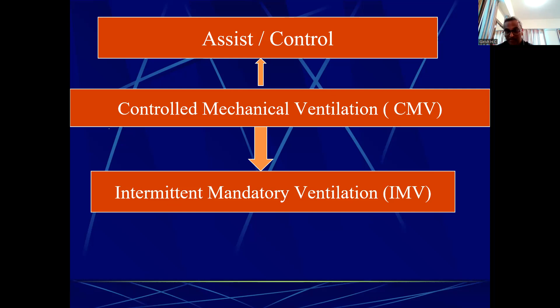Then intermittent mandatory ventilation. So the problem with assist control was that every time the patient made an effort, it gave a breath. That means if the patient is breathing 60 per minute, it gives 60 breaths, with a lot of pressure. So there was a chance for hyperventilation, because the technology was not there to allow the patient circuitry so that the patient can breathe normally in between the mandatory breaths. So that came later as intermittent mandatory ventilation. But still, this was not good enough, because you may be exhaling and the machine may be inhaling, or you may be inhaling and the machine may be exhaling. There was no synchronization of the breaths.